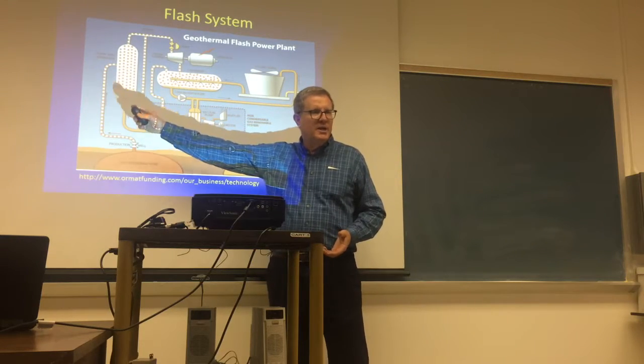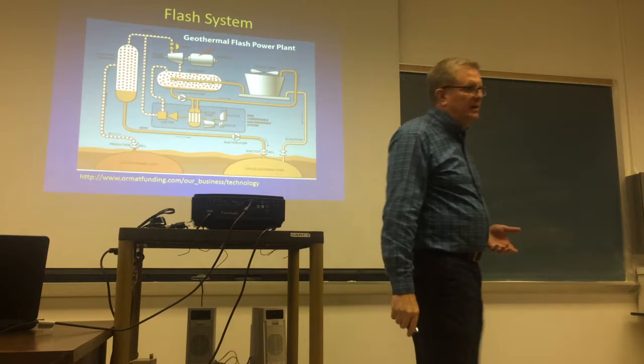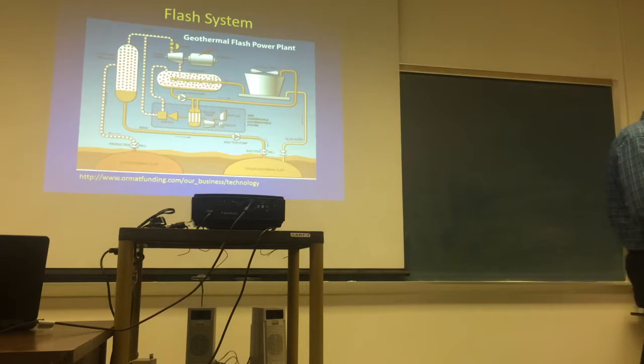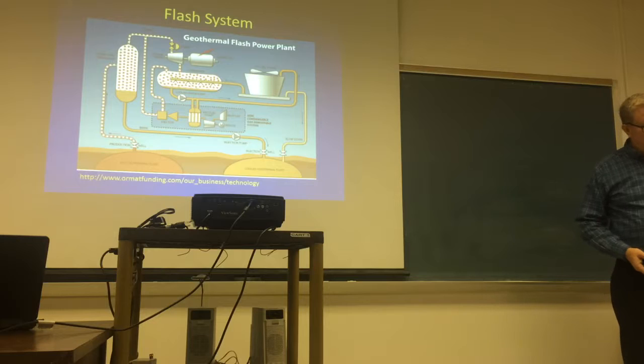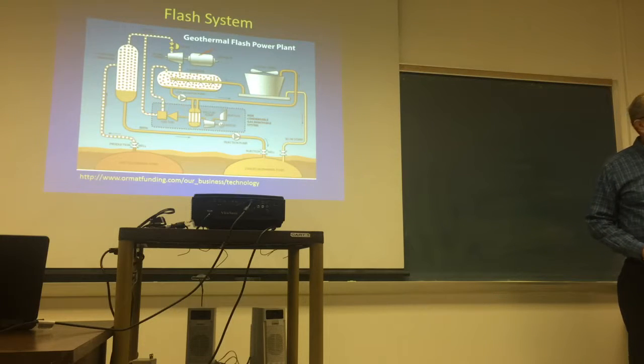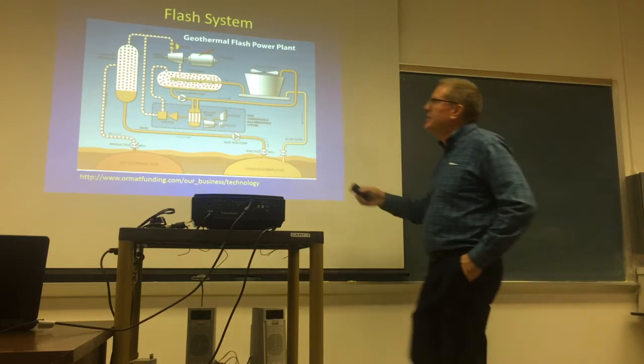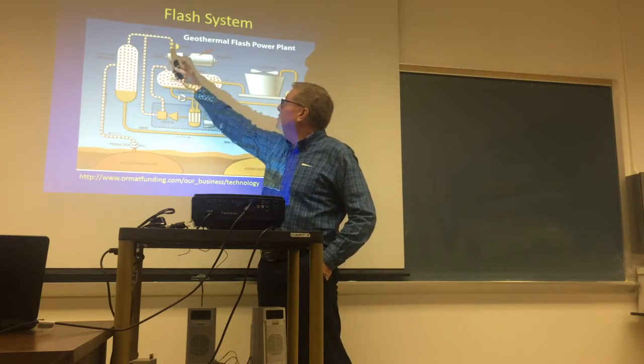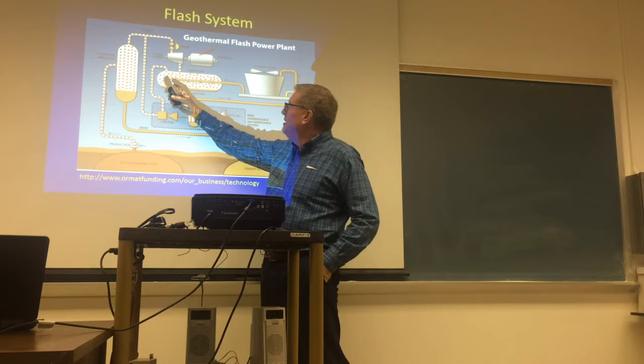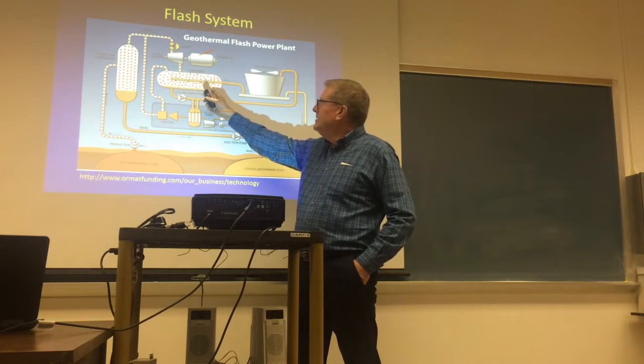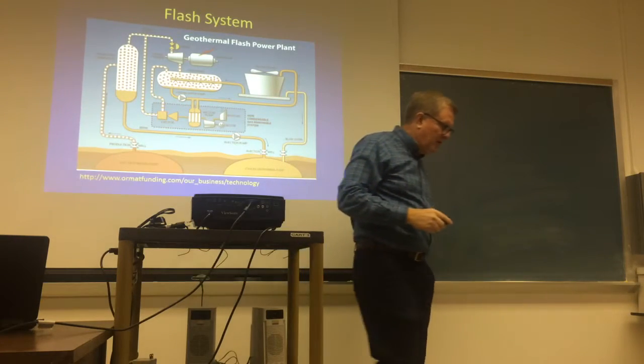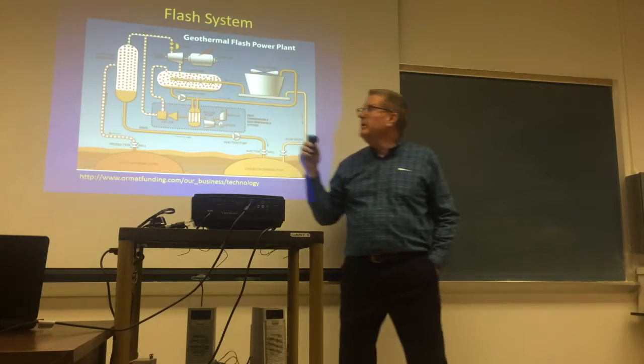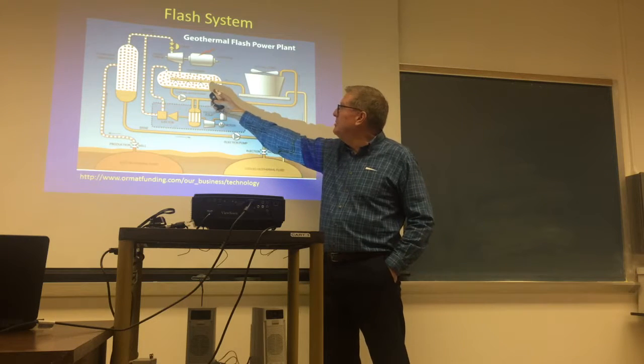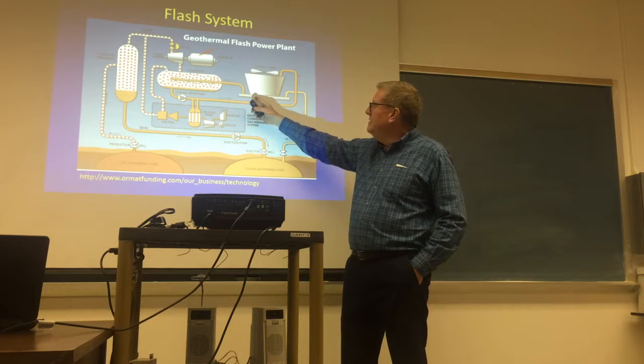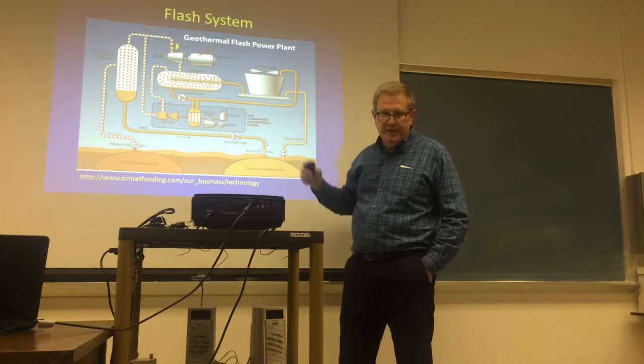So if you have hot water at say 300 degrees and it's at 50 psi thereabouts, it's still going to be under pressure like that. It's not going to flash, but once you take the pressure off of it, the water flashes into steam. So the steam vessels then collected the steam and ran the turbines, and then they would have condensers on the tail end of that. That's much like the technology of how a coal-fired power plant works - steam going in and then condensers after the turbines. And further to that, you have recirculating cooling towers cooling the water.